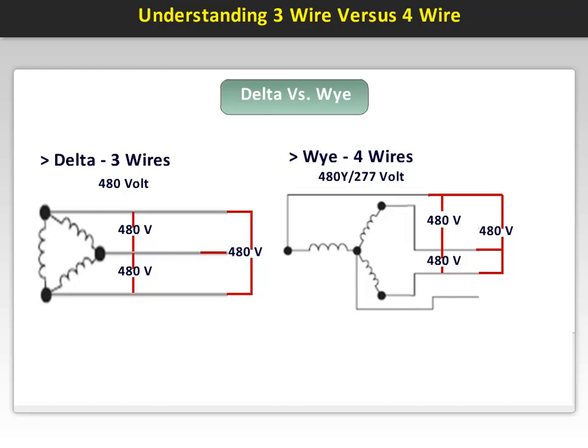A voltage of 277 volts is achieved by connecting any phase-to-neutral. Phase A to neutral, phase B to neutral, or phase C to neutral becomes 277 volts single-phase. This voltage is very popular for industrial lighting in factories.